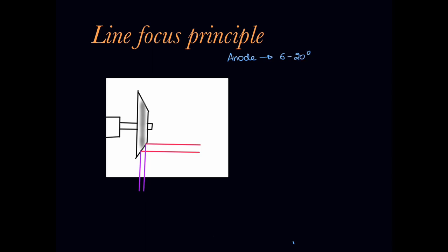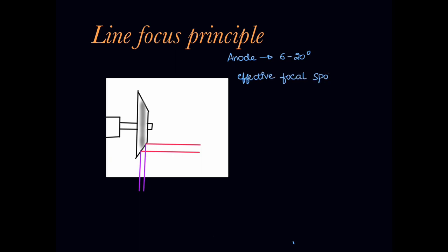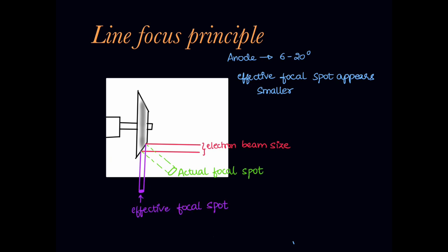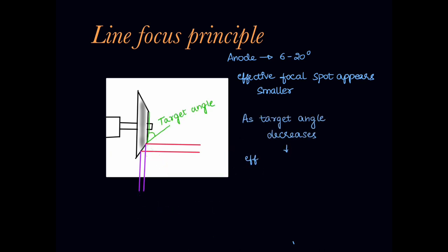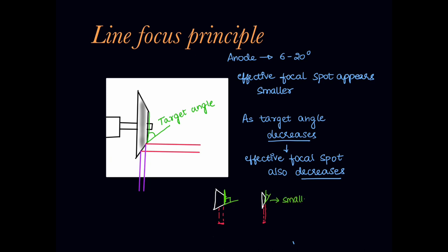In this video, we will discuss the principles on which the x-ray tube operates. The anode, usually the rotating anode, is kept at an angle of 6 to 20 degrees, also called the target angle, in order to focus the primary beam towards the patient. The electron hits the target at a focal spot, but when visualized from the angle of the patient, the effective spot will be smaller than the actual focal spot. This principle is called the line focus principle. As the target angle decreases from 20 degrees to 6 degrees, the effective focal spot size also decreases — the smaller the angle, the smaller the effective focal spot.